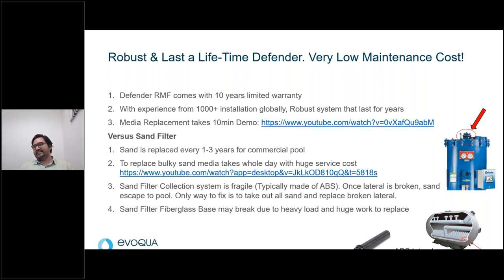And lastly, the base of a fiberglass sand filter is also made out of fiberglass. Over time, because of the heavy load, it will exhaust the strength of the fiberglass and may crack as well. Therefore, it will be a lot of work to replace the base or even the whole sand filter.